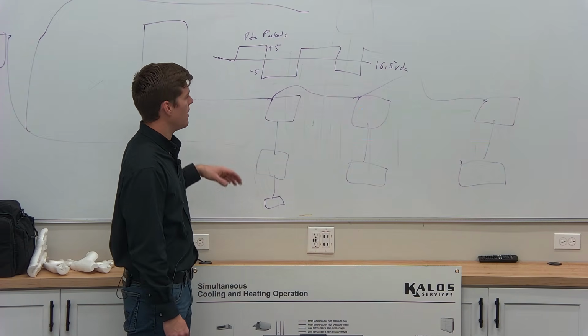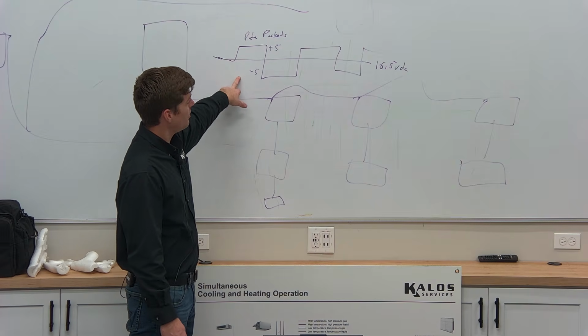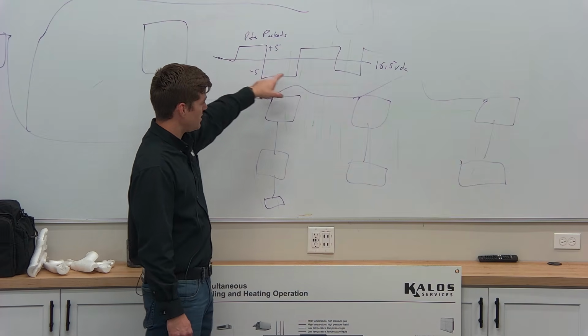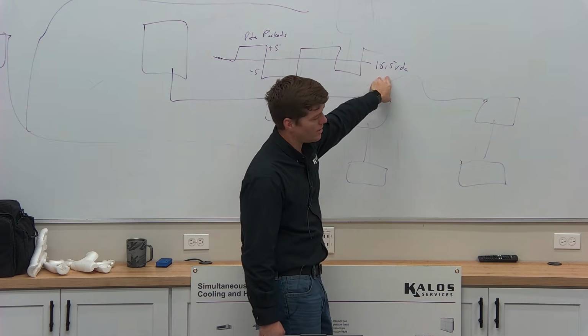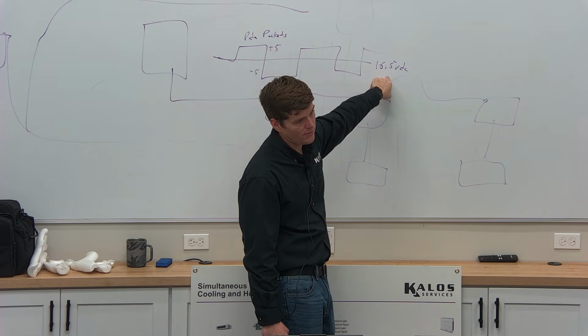It's extremely helpful when you guys are working on systems like this and you're trying to understand that. But this is just the communication protocol. And so there's going to be a carrier wave, which is the 16.5 volts DC. So when I go between F1 and F2, I'm going to see 16.5. If I have a lot of fan coils connected and it's a lot of wire, it might be 15.4. As long as I'm above 14.7, that's all that matters.